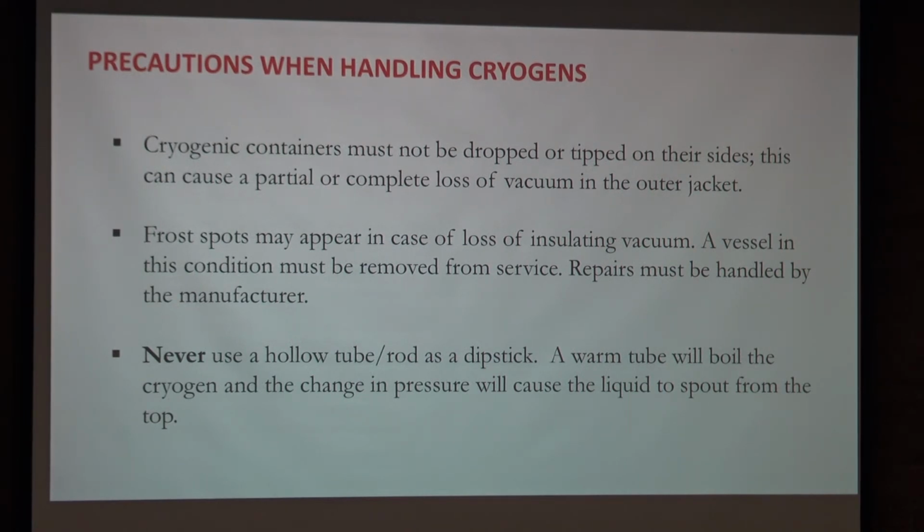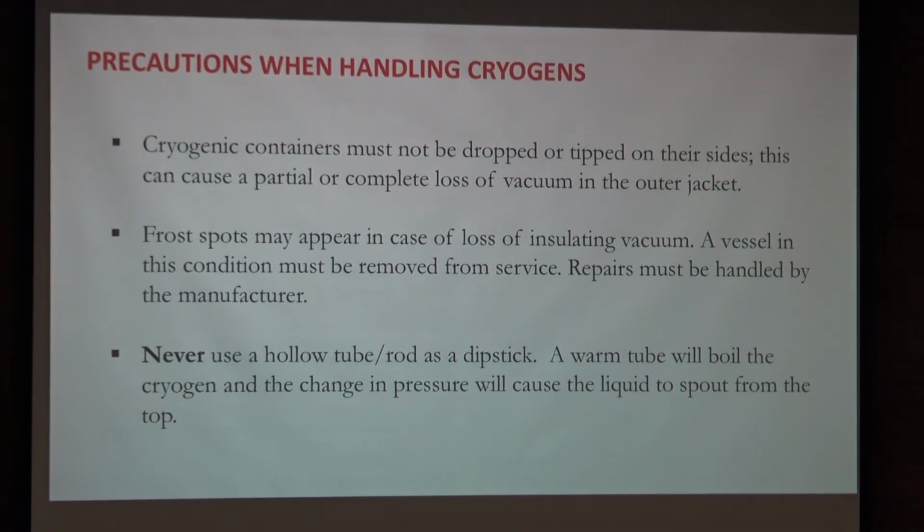rapidly evaporate and expand. Inspect your transfer dewar for frost spots, where you see some condensation on the outer wall of the dewar. That's an indication that the insulation is partially or fully gone bad, and the dewar is dangerous to use and needs some repair.